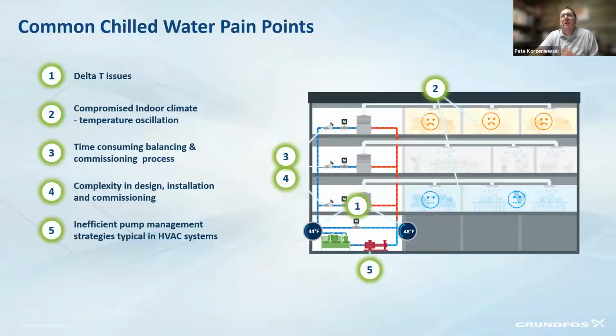So we look specifically at chilled water systems and what the pain points are. The biggest one, and Justin talked a bit about it, is the delta T issues, or those temperatures returning back to the chiller. If we're not giving the chiller the appropriate temperature that we had designed for, we're going to see a lot of issues with cycling, which are going to lead to other problems.